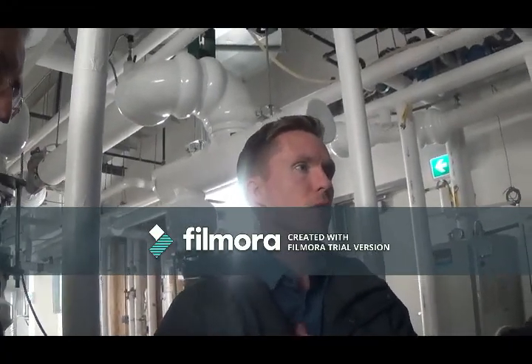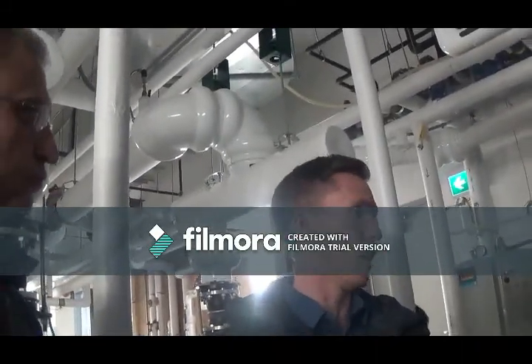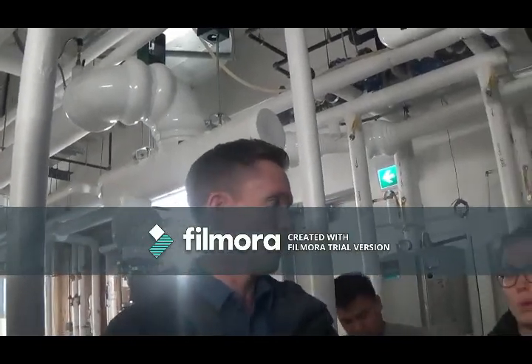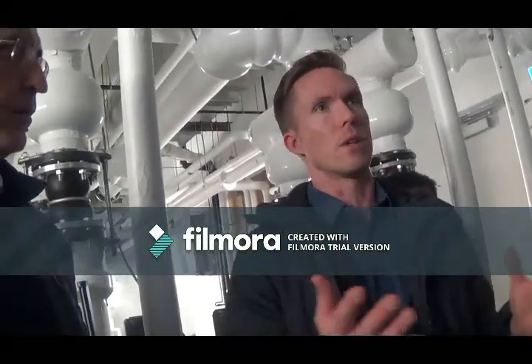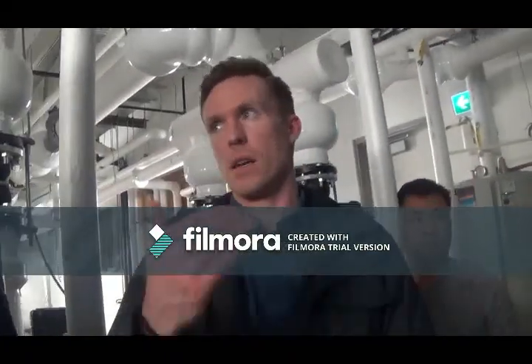And that's pretty much it. From a superintendent building management standpoint, that's probably as far as you want to go. I can show you quickly how to isolate away from the BAS if you want. It is pretty straightforward, and you can always give us a call to do that if, for whatever reason, building automation just isn't working. Since it's sending a set point, it could be wrong, it could be sending something too low.